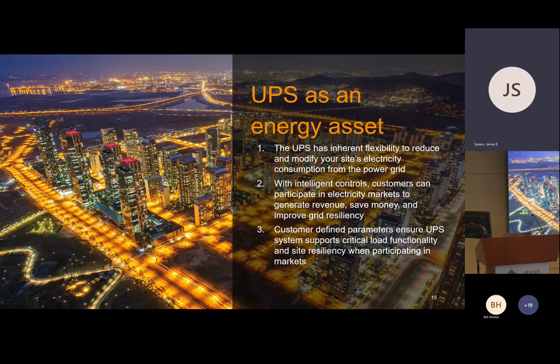The difference is lithium batteries open the door to this kind of operation, mainly because they have a 10-year life, and more importantly, because they're more amenable to lots of charge-discharge cycles compared to traditional lead-acid batteries. This allows the user to do a couple of things: take advantage of time-of-use electrical rates by skimming power off the battery, and shave the peaks for their facility to protect against cost, so they don't set a demand charge that increases their utility bills for the next 12 months, by using the battery as a buffer.